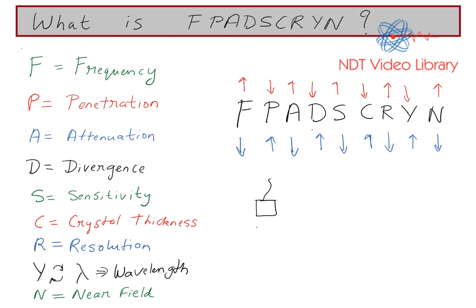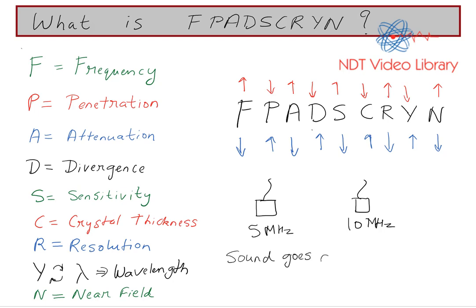Let's take an example. Consider two transducers: one at 5 megahertz and the other at 10 megahertz. The question is, which of those two probes will sound penetrate deeper? 5 megahertz is a lower frequency compared to 10 megahertz. Looking at FPADSCRYN, lower frequency gives more penetration. So sound will go deeper at the lower frequency — the answer is 5 megahertz.